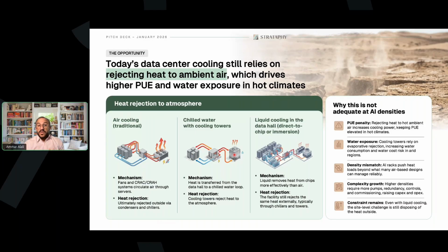The common method that we hear about everywhere for data centers is liquid cooling. And again, there are different variations of liquid cooling, from direct-to-chip to immersion cooling. So you're using some sort of dielectric fluid, typically an oil, to immerse these chips, typically GPUs, to take the heat away faster. So the heat transfer from the hardware you're trying to cool, which is the chips, to the fluid that takes the heat is direct and more efficient. So you're improving the efficiency significantly in this piece, but then you have some sort of heat exchanger between whatever fluid you use in immersion cooling and, typically, water on the other side. Then it goes to the heat rejection function. And that could be the dry cooler, which is literally just a fan blowing on the water to dissipate the heat, or some sort of evaporative-based cooling.